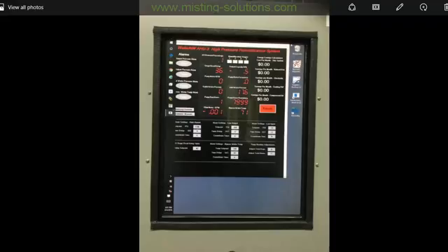A few finishing words on zone control. I talked about the 10 stages of humidification using 4 zones. In the training seminar, I used 2 zones, 2 nozzles per zone. Here I talked about 10 stages with 4 zones. Let's look at it a little differently. Let's say there was 1 nozzle on the first zone, 2 nozzles on zone 2, 3 nozzles on zone 3, and 4 nozzles on zone 4. If you add those up, that's 10 nozzles. If you bring each zone in one at a time, then start to overlap those zones until you have all of them on, you have 10 stages.